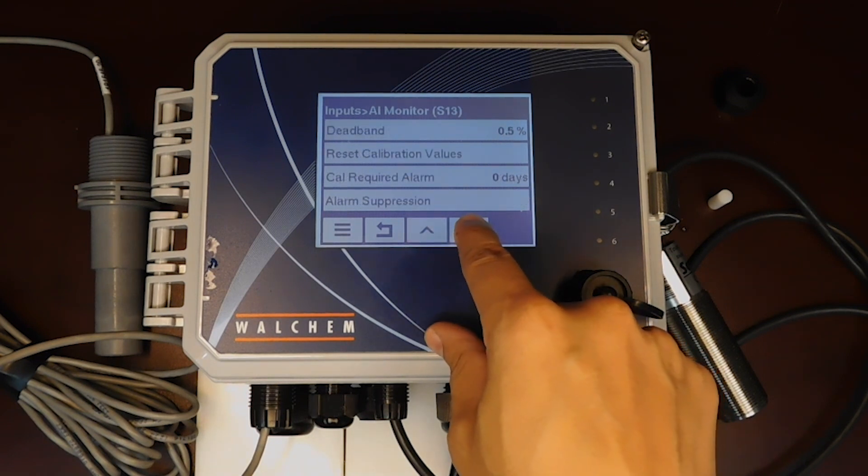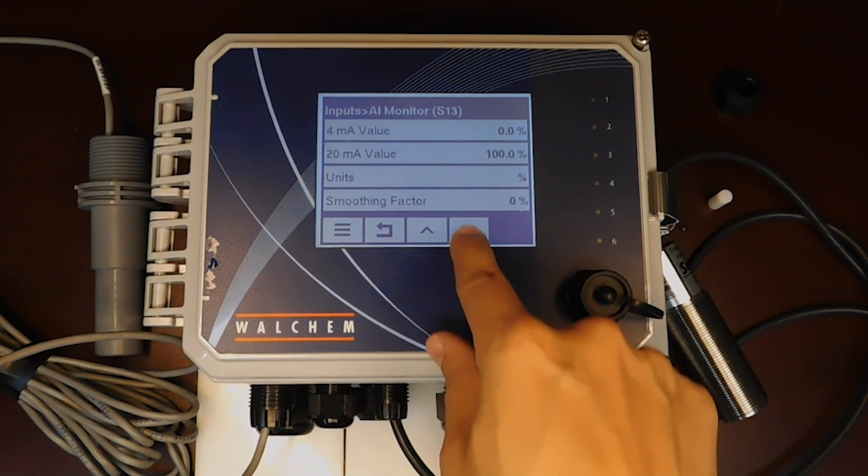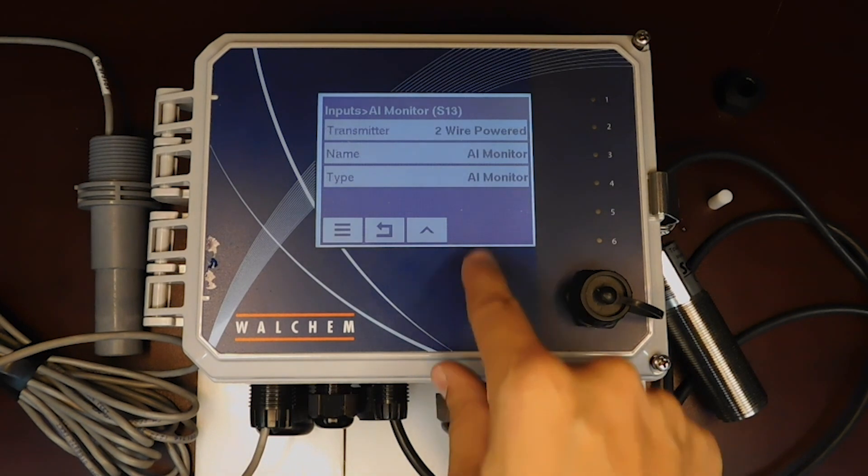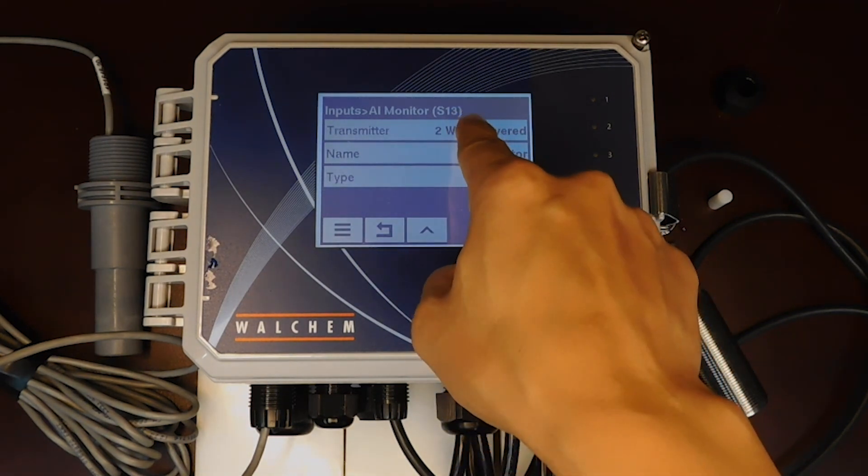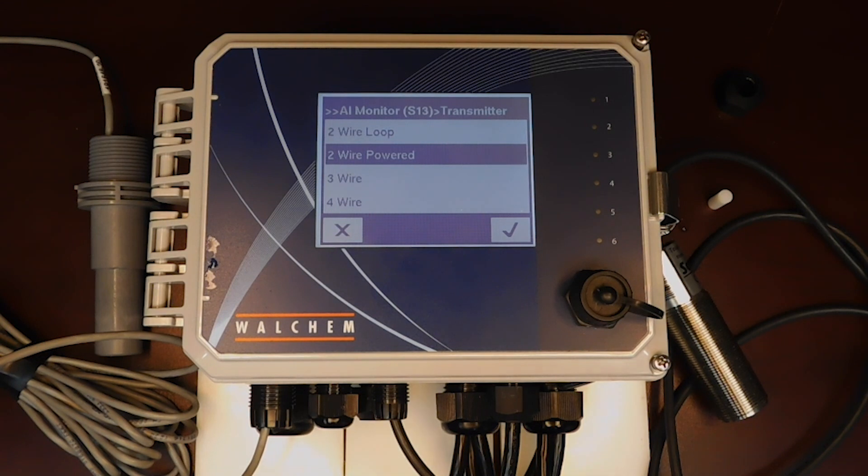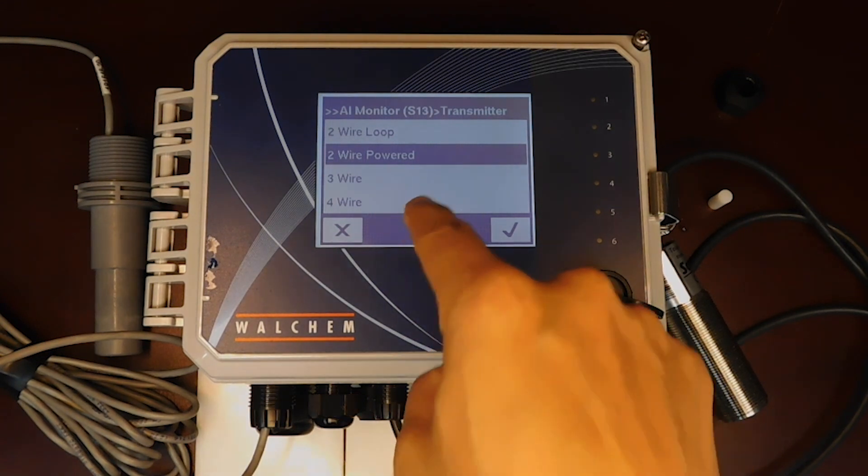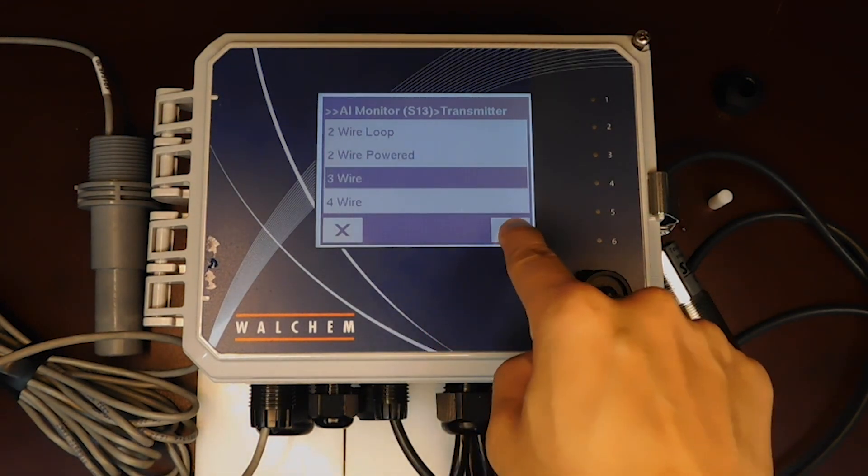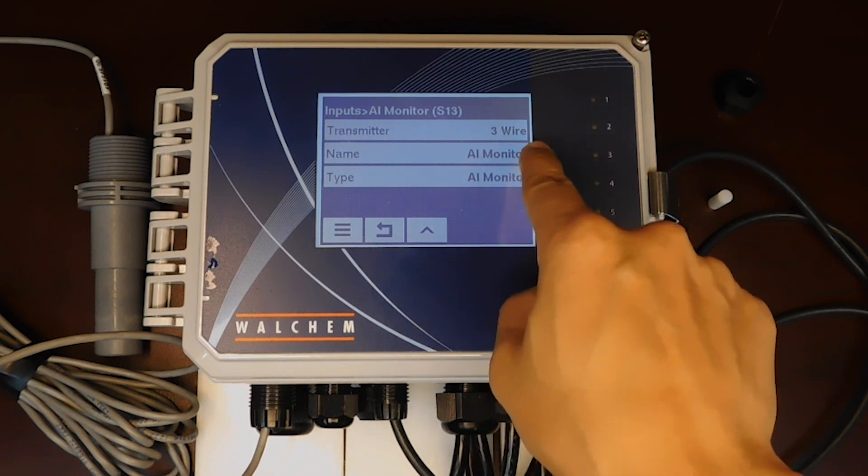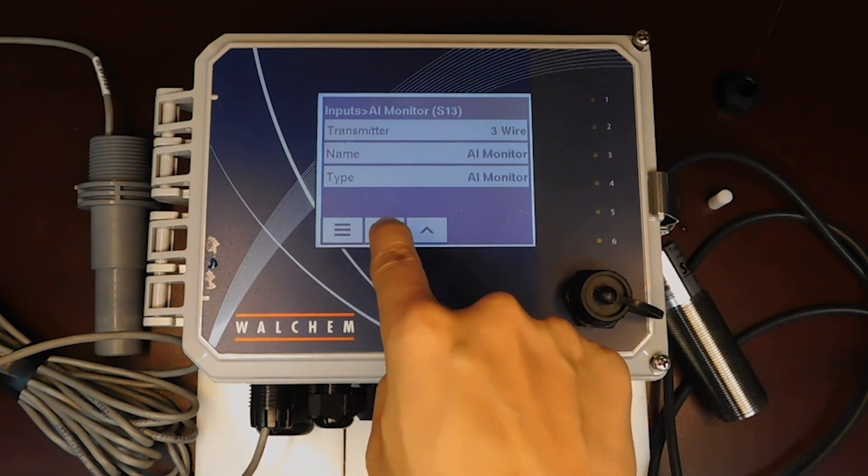You can see that you can have the option to set various alarms for certain distances. First, we're going to scroll down. We're going to see transmitter is currently set to two wire powered. We said this was a three wire transmitter, so that's the setting we're going to put it to. Select that, press the check mark.